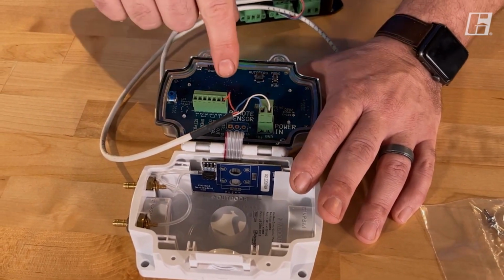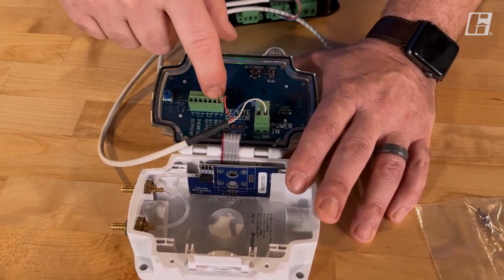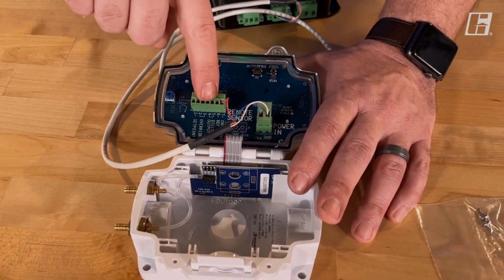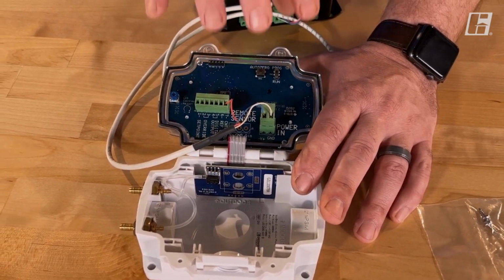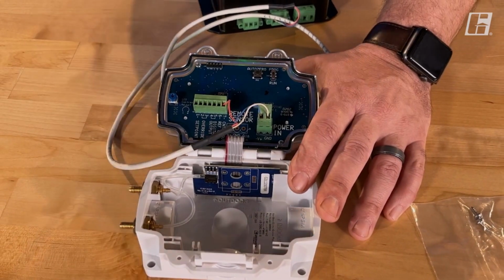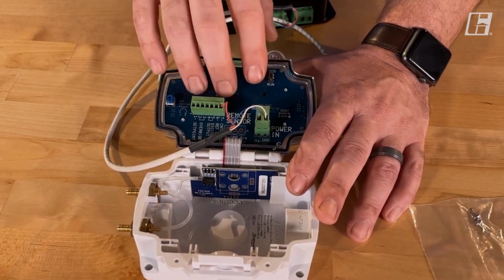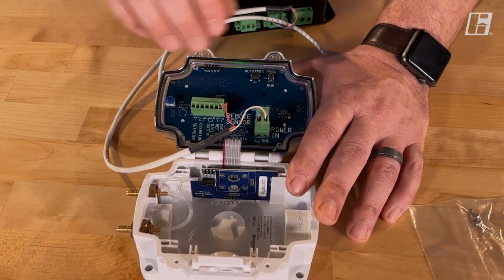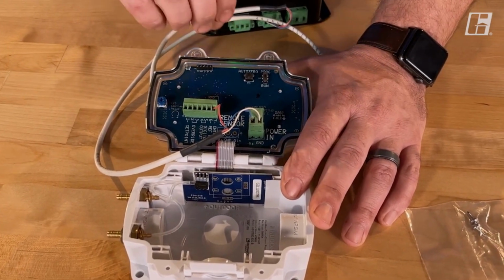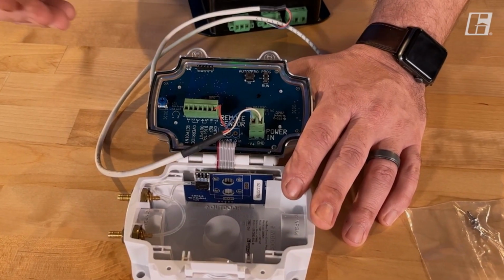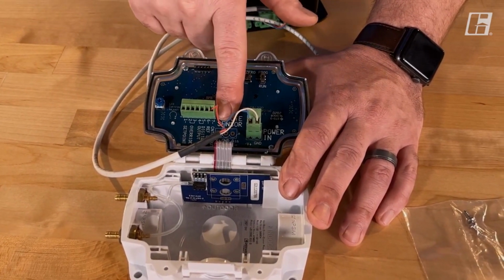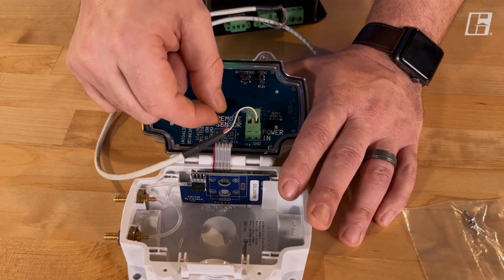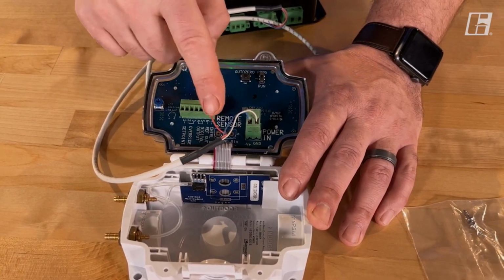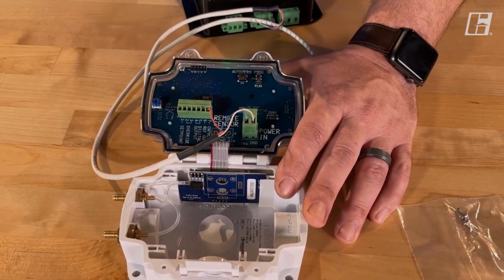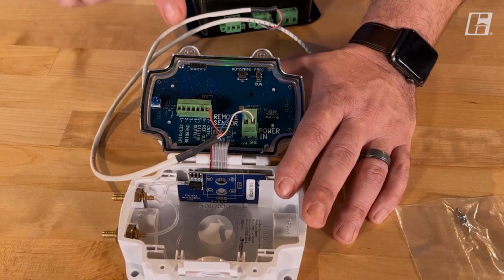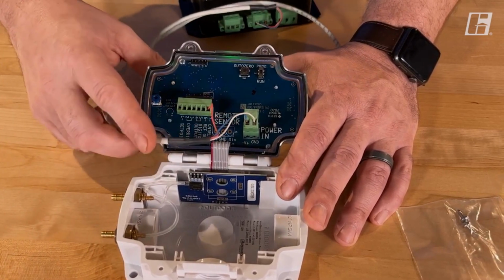We also now have a reference output, that's the 6th terminal. The reference output is a 0 to 10 volt signal this device can send to a building management system, and it reports its current CFM or current pressure, depending on which mode you've enabled, and tells them in that 0 to 10 signal what that is. The 7th control output terminal, that's our 0 to 10 that goes to the fan. This tells the motor how fast to go to maintain your set point. We'll actually go through those menus in the second video of this series.